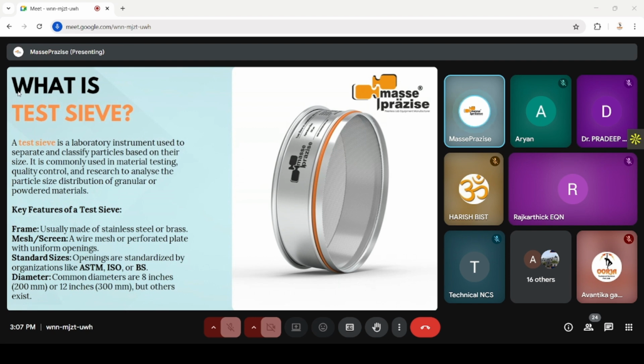The third part of the test sieve is a rigid frame on which the wire mesh is uniformly tensioned and welded with precision. And the fourth part is the silicone o-ring. Basically, the silicone o-ring works as a reducer of noise during the sieving process, and it also controls the particles coming out from the top of the sieves.